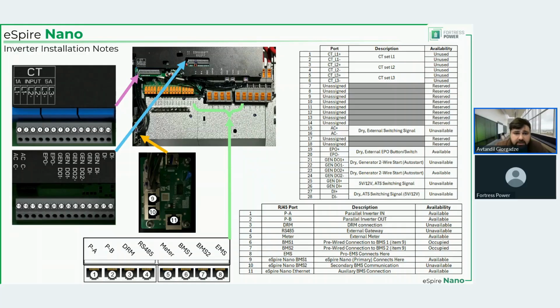So let's start with regular ports. The first 6 are for CT sets. That's for L1, 2 of them, for L2, another 2, and L3, again, 2 ports. But they are unused because we made the meter mandatory, right? Because we are trying to avoid the potentially negative consequences of using just the CT: inaccurate readings, bad contact, stuff like that. And also, the meter gives us way more accuracy, and at a longer distance, the meter is way better than the analog signal that is coming from the CTs.